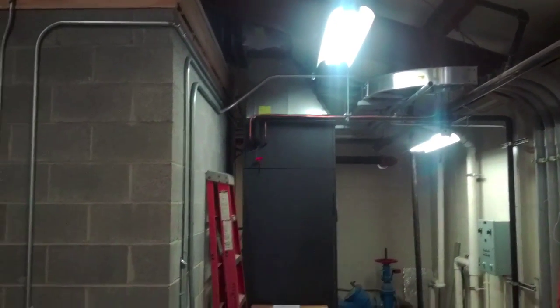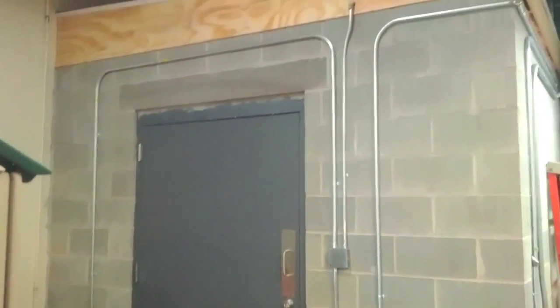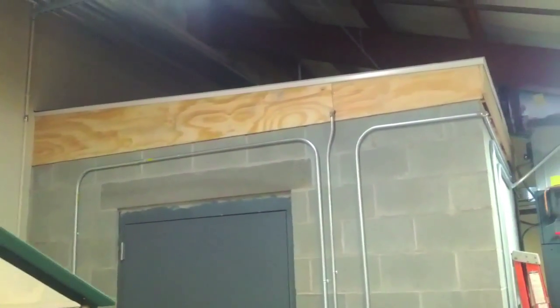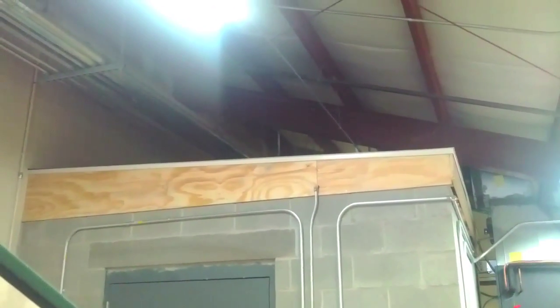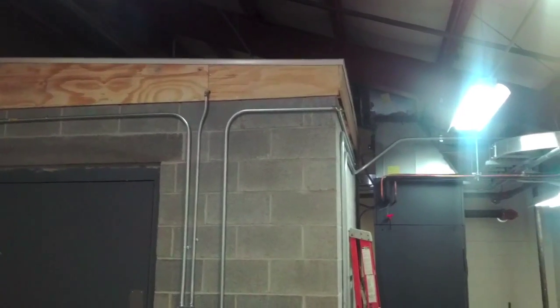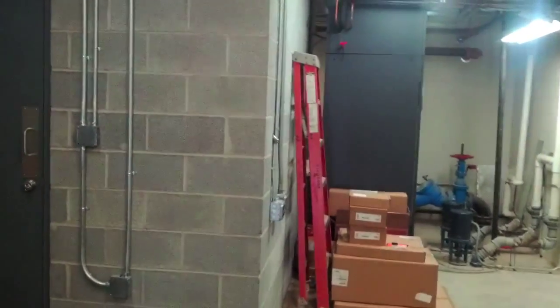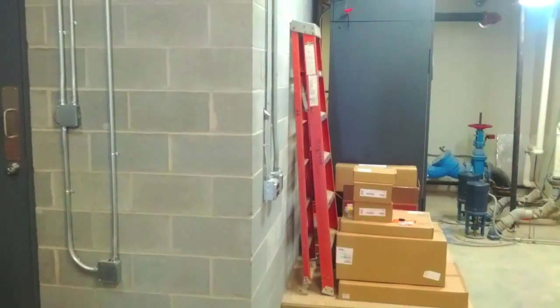From this corner, you can really see that we just have a room within a room, built by our facilities department. They built us a 10x10x10 concrete block room, finished it off with insulation and drywall, with a nice four-foot wide door to bring equipment in, and provided us with a gently sloped roof on the top — because of the fire sprinkler heads that exist over the room in the outside room. If one of those pipes were to burst or the sprinkler head were to malfunction, the room could easily have pooling water on top. We've also provided a couple of outlets here on the outside, controlled by a switch on the inside.